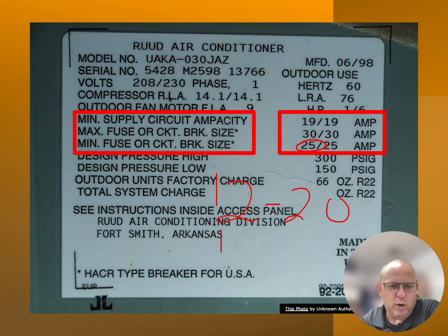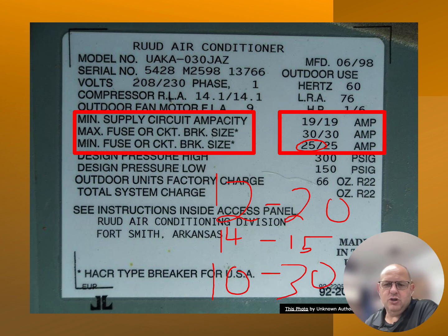Can I put a 14 gauge wire in there? Absolutely not. The 14 gauge wire is good for 15 amps. If I put a 25 amp breaker in there, I'm burning that wire up. It's not going to be able to handle the amps that particular unit's going to be running. NEC says a 10 gauge wire is good for 30 amps. Can I install a 25 amp breaker on a 10 gauge wire? And the answer to that question is yes, because the 25 amp breaker will trip and the 10 gauge wire is capable of handling up to 30 amps of electrical current going through it.